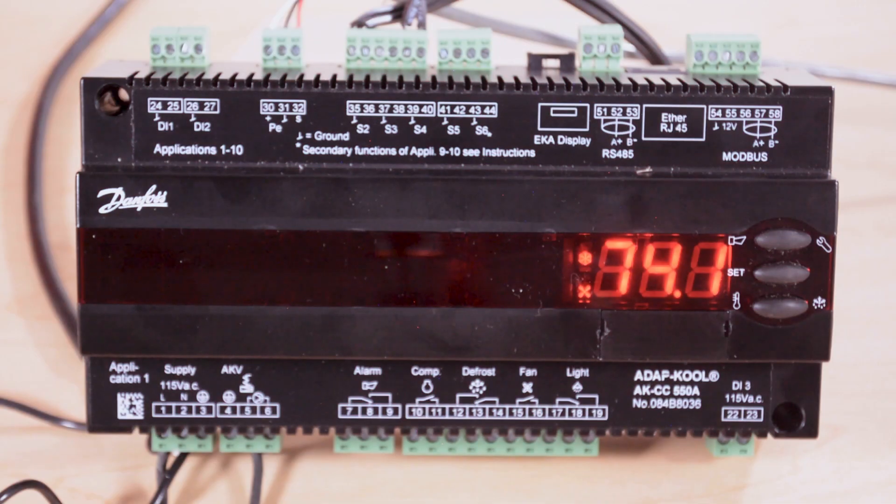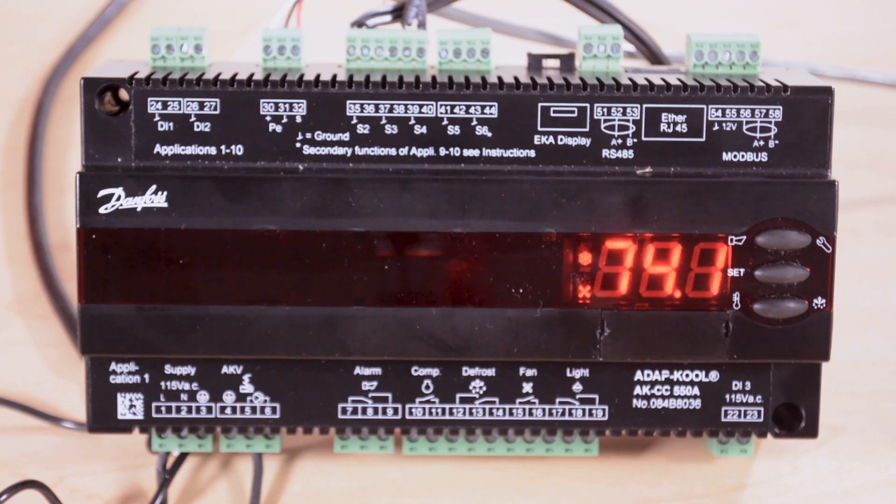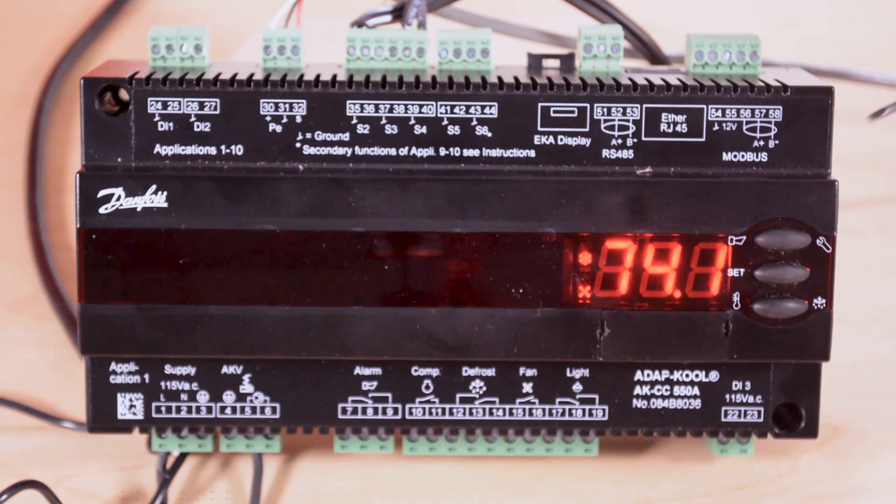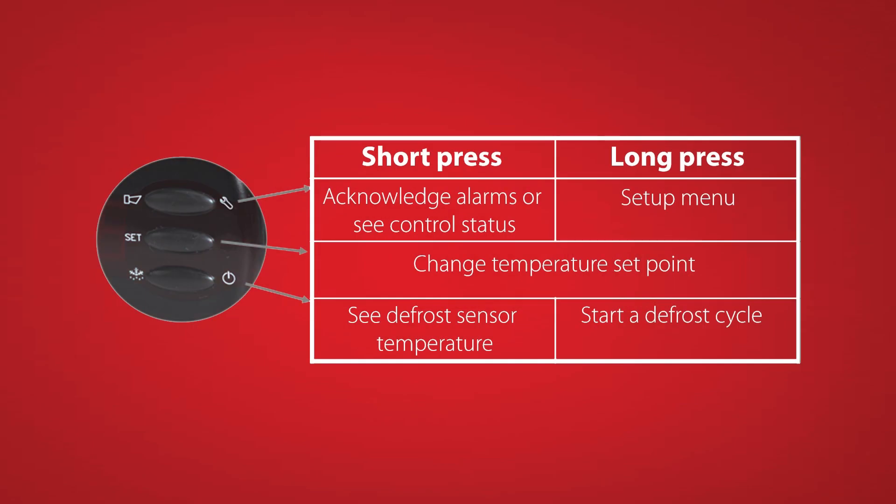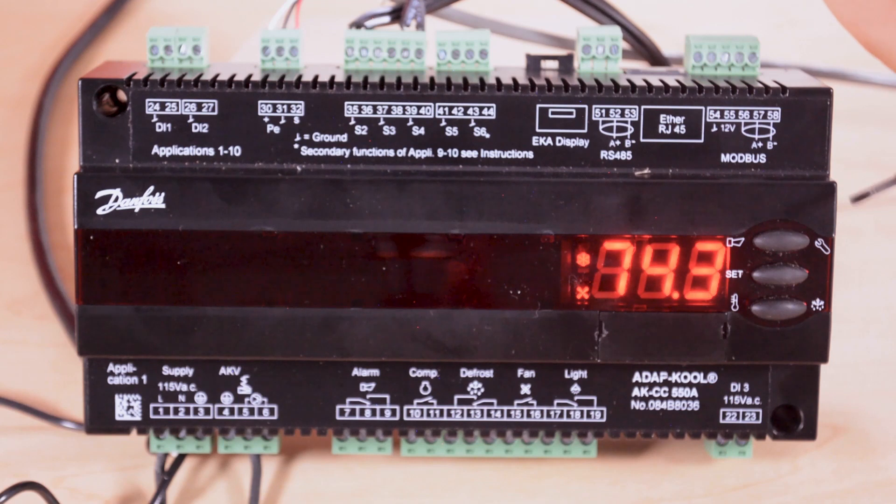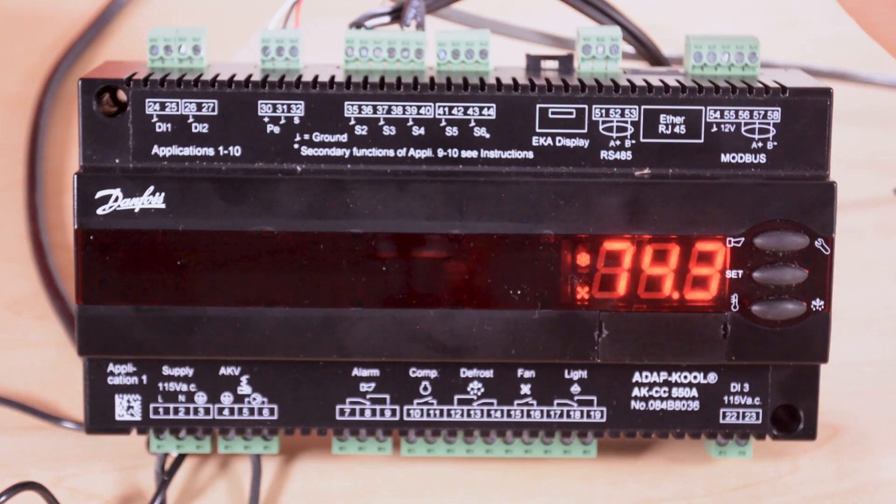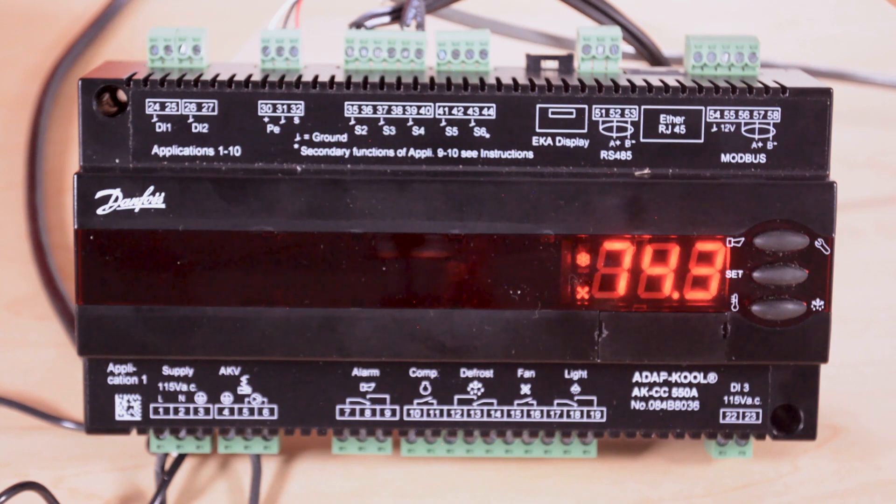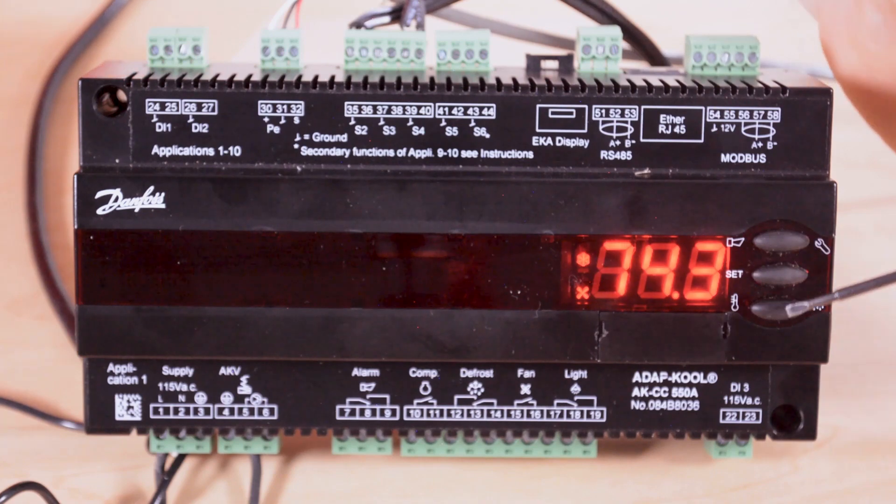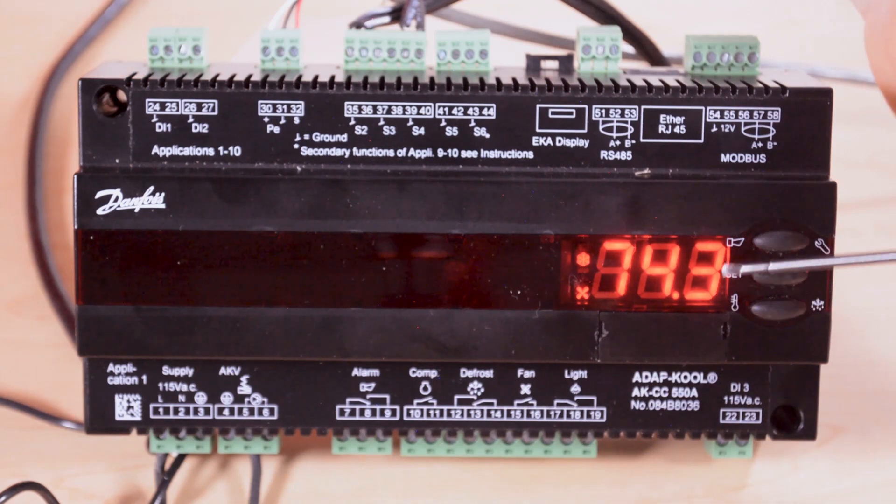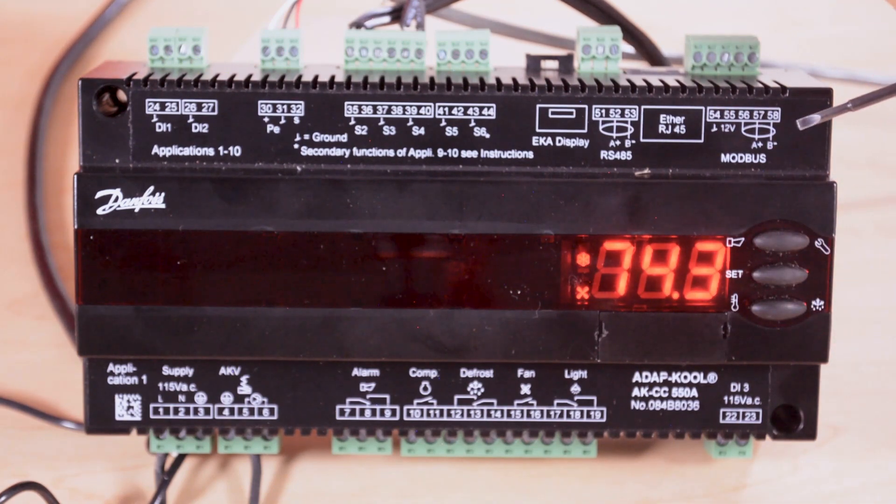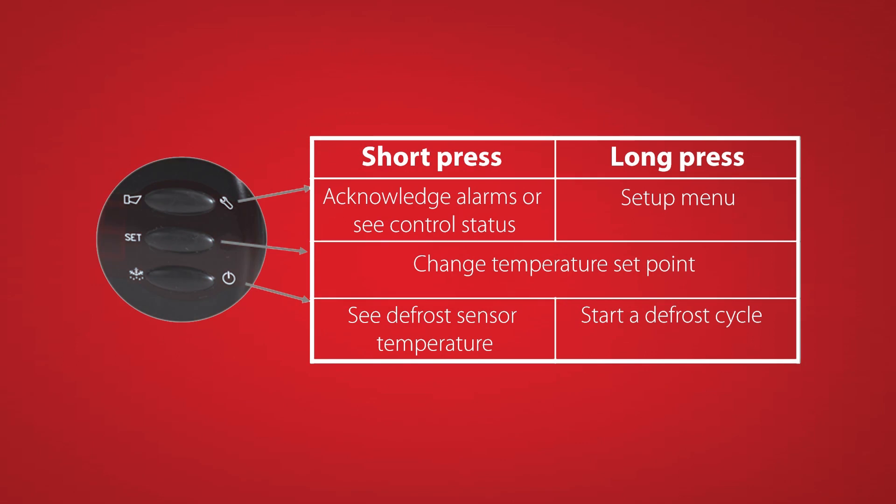For the button usage on this controller we have three buttons on this side. The top button will give us status codes on the controller. These status codes such as this one could be telling us what the controller is currently doing. If we press it again we would get an alarm code if one exists, but if there is an alarm in the controller you'll see these icons on the side will be flashing.